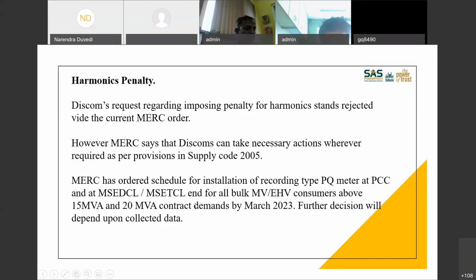This is there in the order. Those consumers who have their contract demand more than 15 MVA and 20 MVA will have to connect a recording type PQ meter by 2023, and MSEDCL and the consumer will have to keep exchanging data between them at the same timestamps, because recording meters have the possibility of recording all the parameters with a timestamp. So this will probably create some data regarding how much harmonics are consumed, at least by these bulk consumers.